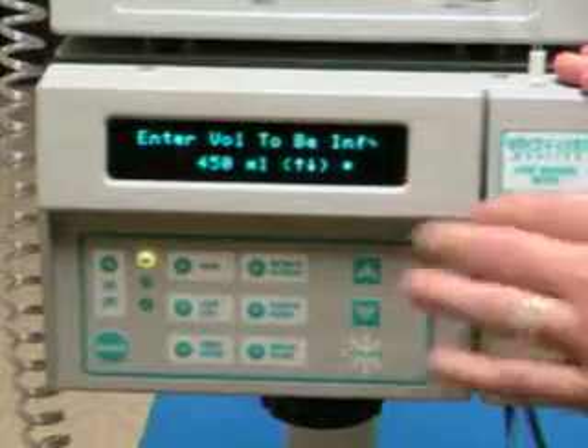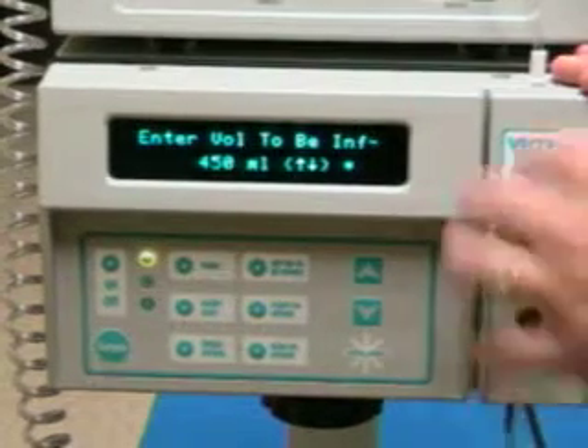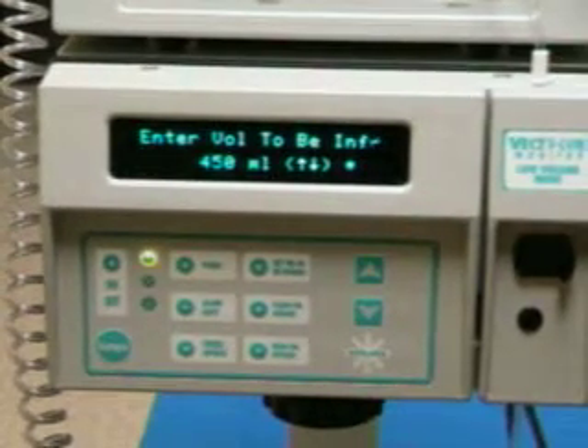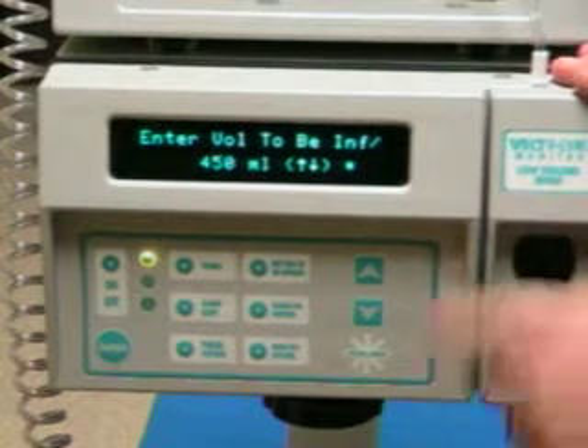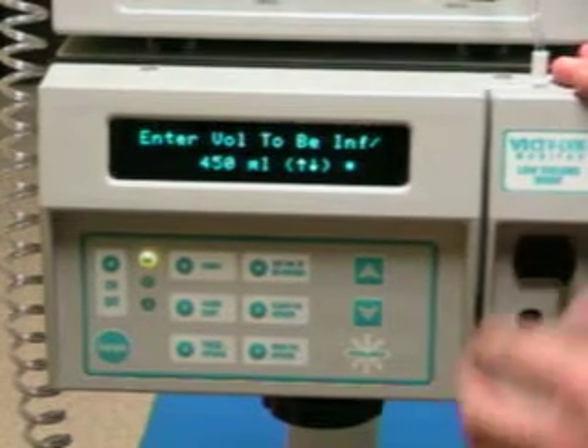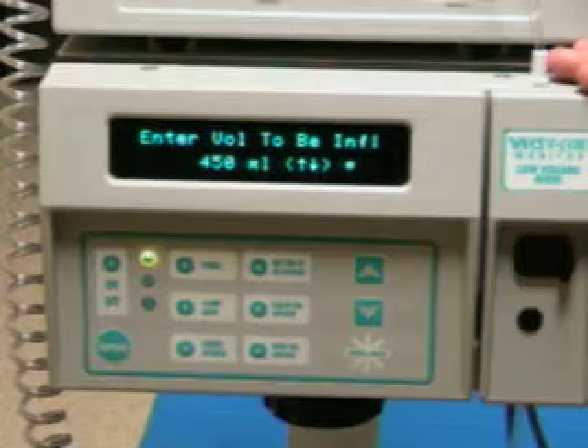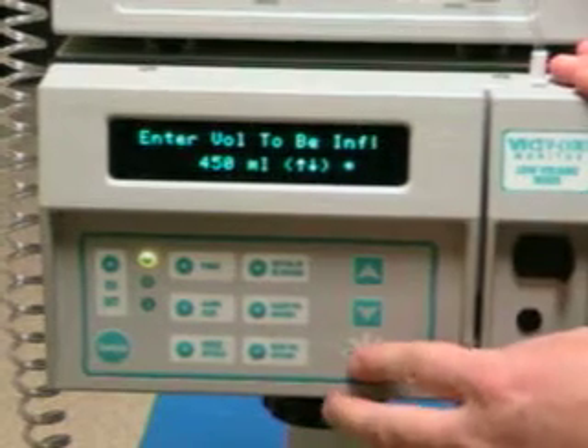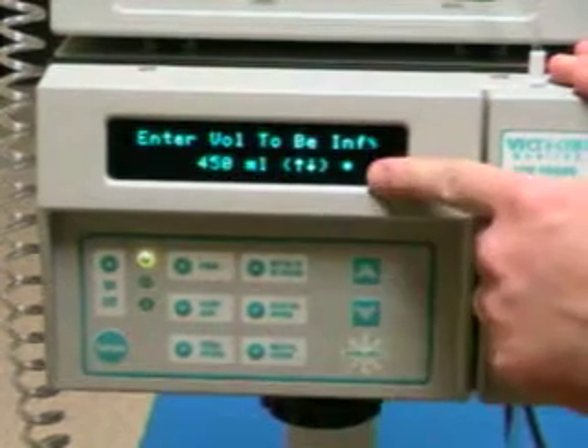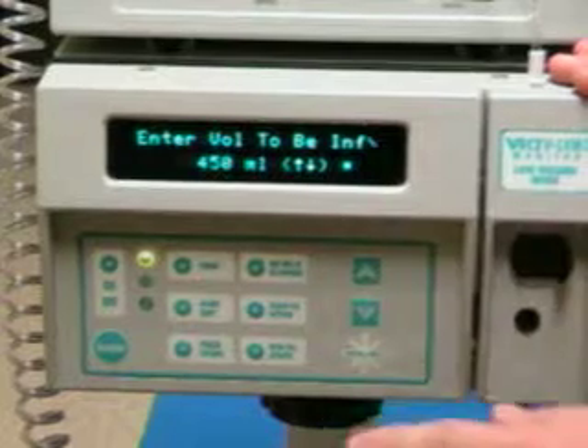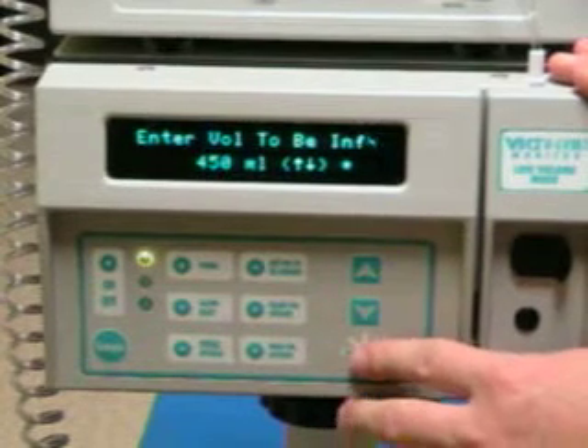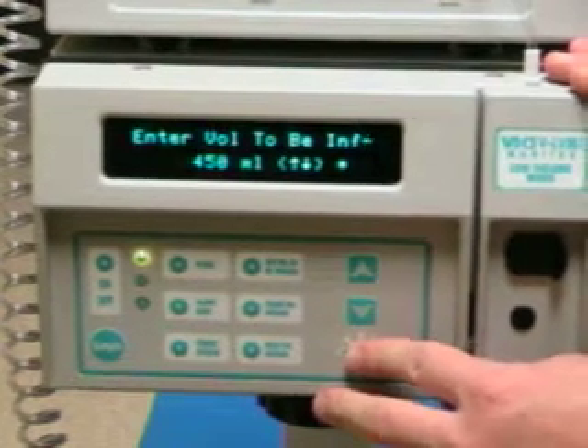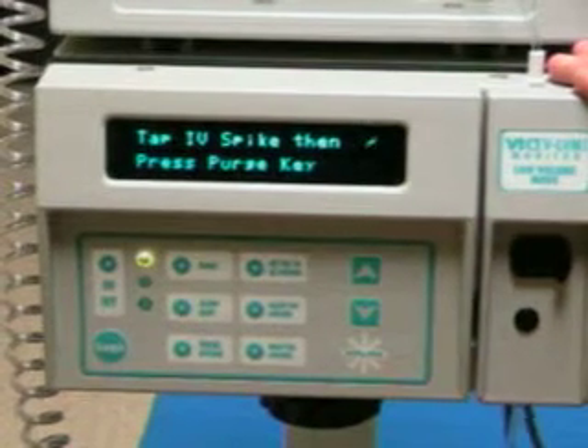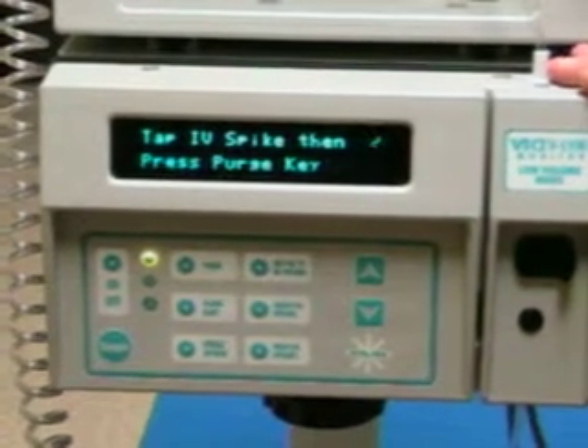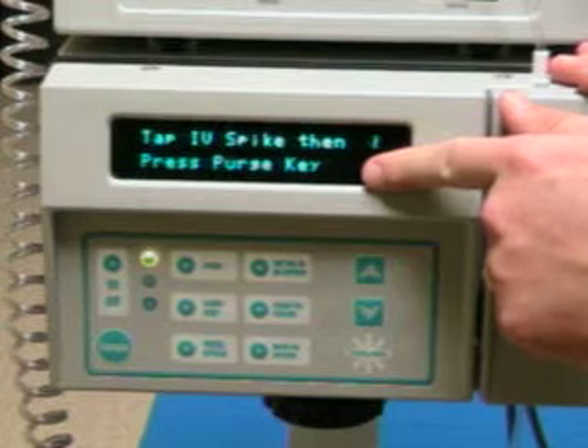Now that's the part that you have to get to within 30 minutes. We're well within the 30 minutes now, but you have to tell it that reference number before 30 minutes is up. Otherwise, the monitor may have a false CO2 reading. Enter the volume to be infused. This is always going to be 450 mils. The machine's going to tell you when you've got 50 mils left in the bag, and it's a 500 mil bag. Tap IV spike, then press purge key.